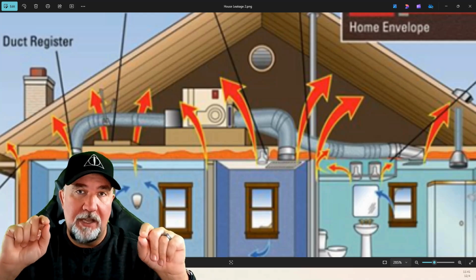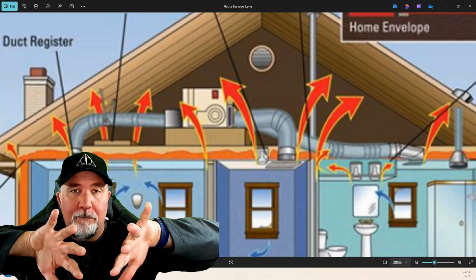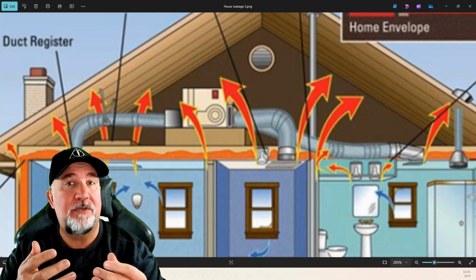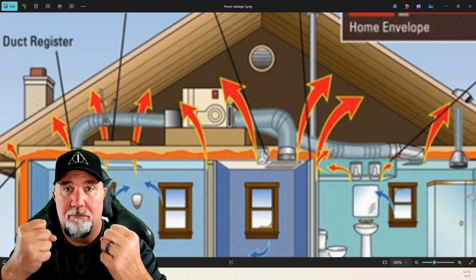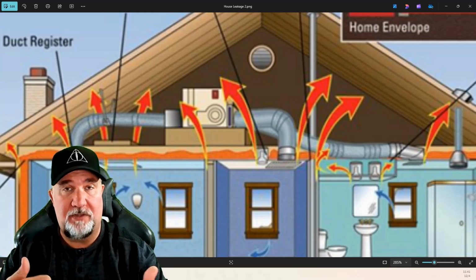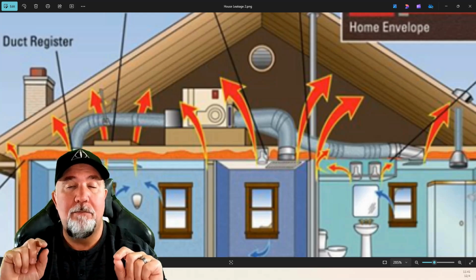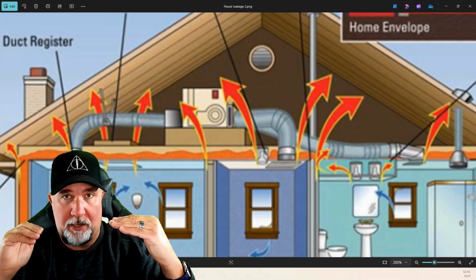So we slightly pressurize the building to help push any air through any cracks, crevices, and things of that nature, and also not allow the outside elements to be sucked in to put the house under negative pressure, because that's what happens, like we talked about last week, where all this stuff from the outside comes in and the moisture ends up embedding itself in all of our porous materials, our couches, our rugs, our different things of that nature, and we run into problems. So ductwork can be a huge issue with this. Making sure it's properly sealed, making sure that it's adjusted correctly, okay?